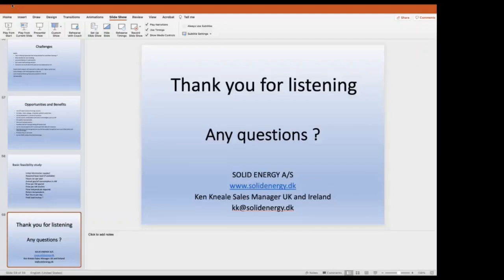Right. Question from Gareth. By the looks of the presentation, your air source heat pump is a split unit, water source heat pump connected to a dry cooler. Is this how you cope with large delta T's, i.e. no requirement for a reverse cycle? No, it's not water. On the air source heat pumps, we can use either glycol as the refrigerant medium in between the components, or indeed we can use propane. So we can then use hot gas from the compressors to defrost. But when we defrost, we send the hot gas back to the evaporators in a cycle, so that the output of the heat pump is not lowered during the defrost cycle.